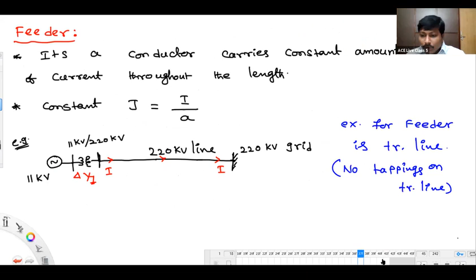But keeping those compensators or controllers may not be economical in the distribution system. That's why at the design stage itself, you take care of that voltage drop by selecting the conductor size, the so-called distributor size. I think all of you are getting my point. Tell me please, all of you getting my point? So I'll write here: the distributor will be designed on the basis of voltage drop criteria. In brackets you write: keeping compensators is not economical in the distribution system. That's the reason why we are moving on to the voltage drop criteria.